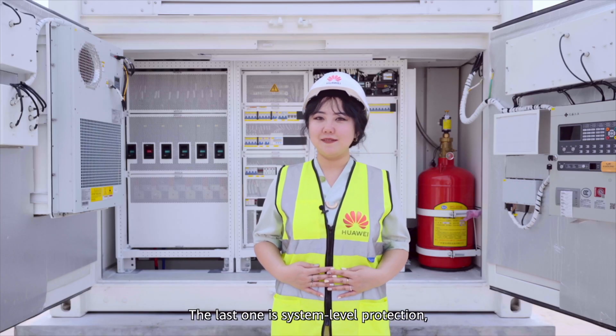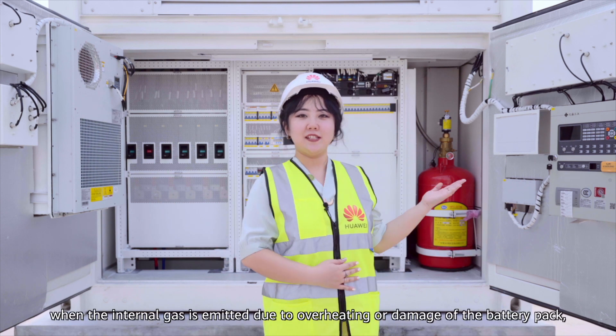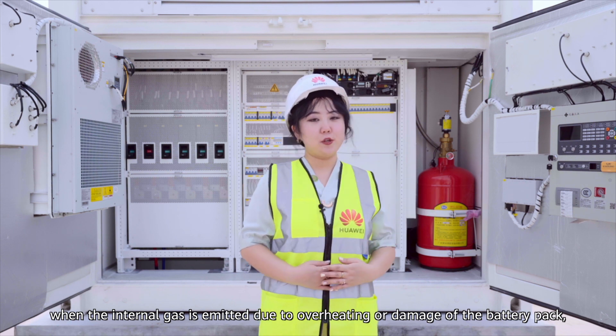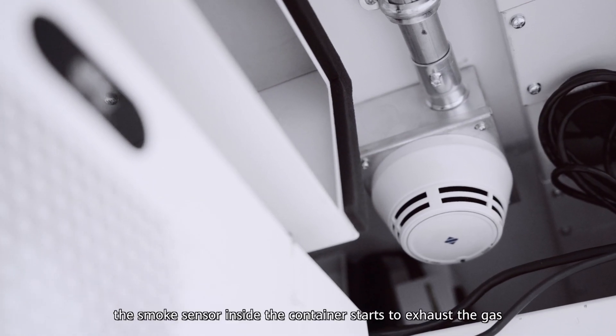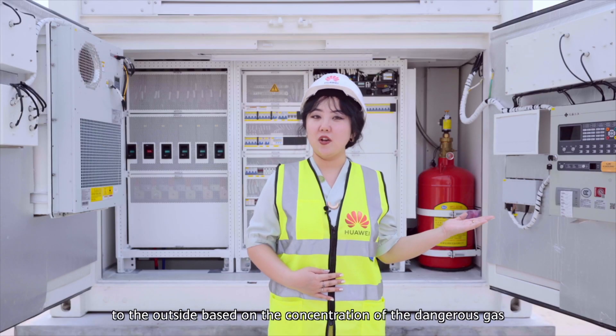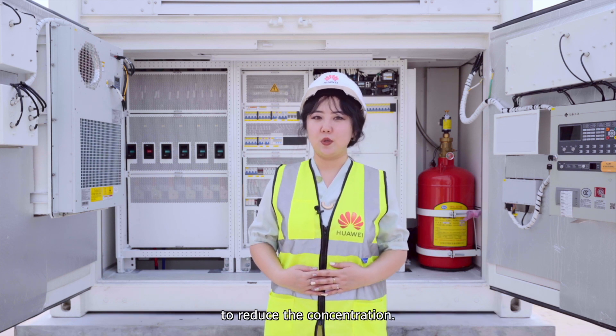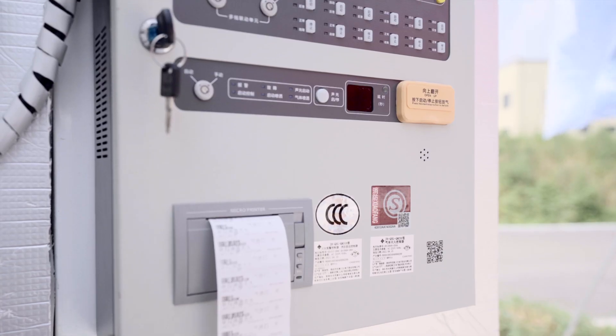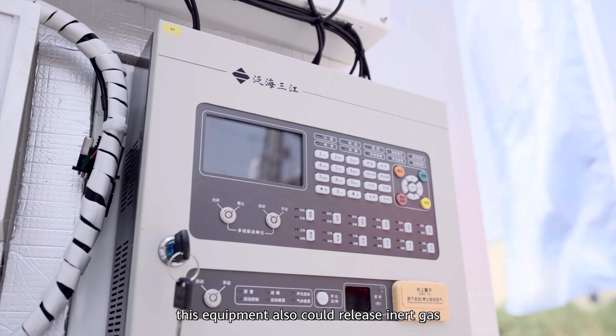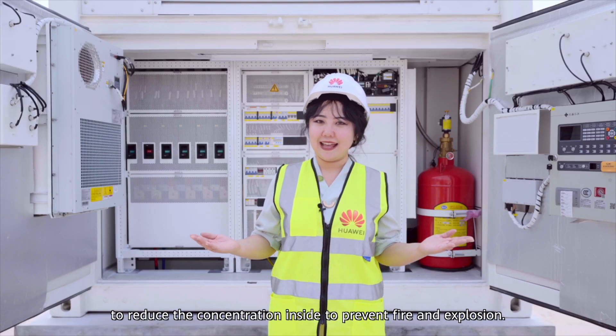The last level is system-level protection. As you can see here, when internal gas is emitted due to overheating or damage of the battery pack, the smoke sensor inside the container starts to exhaust the gas to the outside based on the concentration of dangerous gas to reduce the concentration. This equipment can also release inside gas to reduce the internal concentration and prevent fire and explosion.